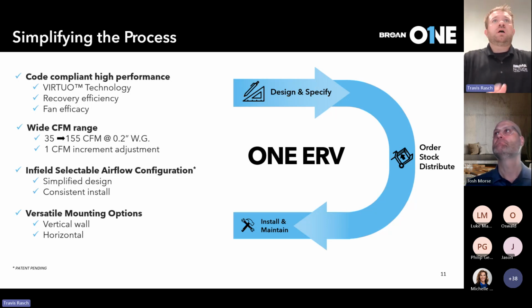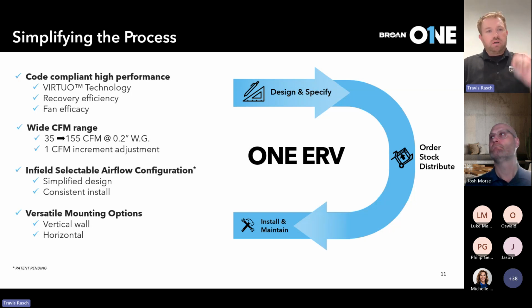Not necessarily between seasons. The SRE is a sensible function, so we're always looking at the outdoor air and indoor air conditions. We do have HVI rated points at the standard temperatures, and you will see a sensible recovery efficiency value. Again, it's going to depend on the outdoor air and what the indoor air condition is. Know that our SRE works the same way: hot goes to cold and wet goes to dry. So the recovery core, for lack of a better term, doesn't quote unquote care which side is which.